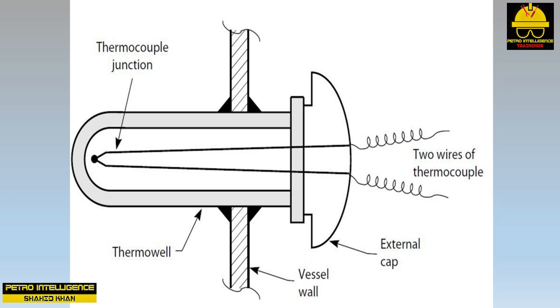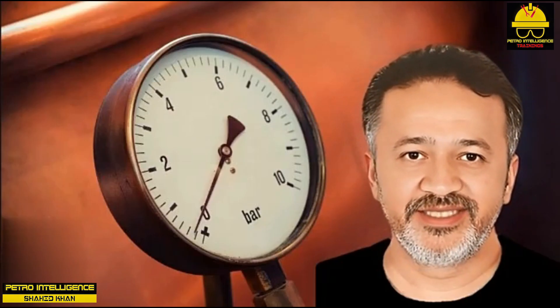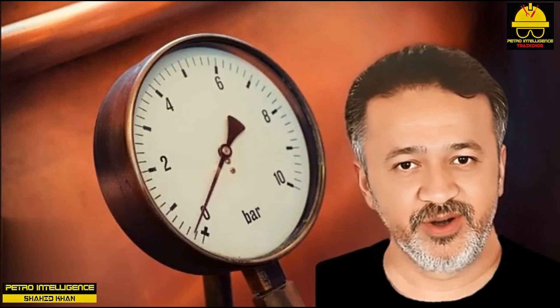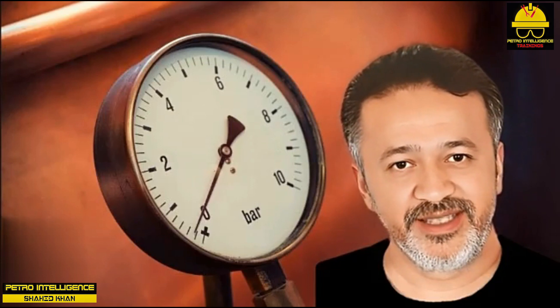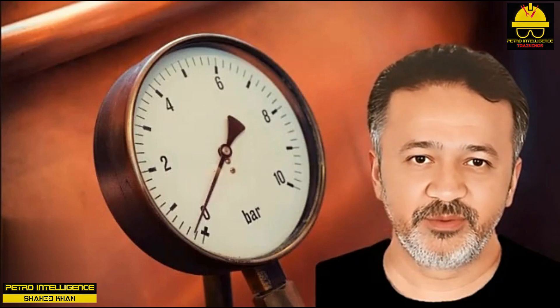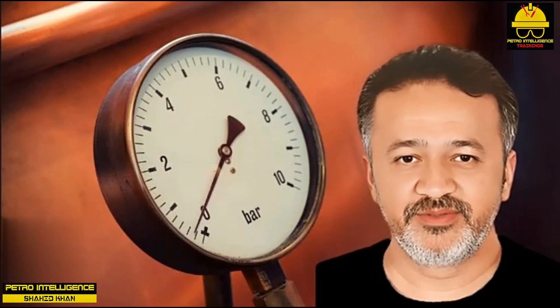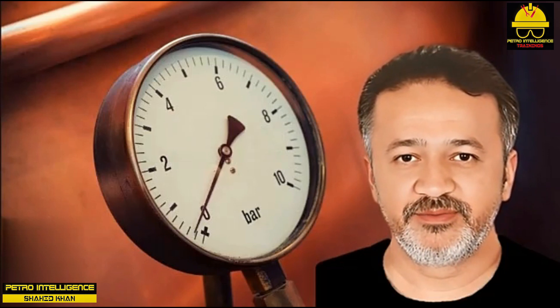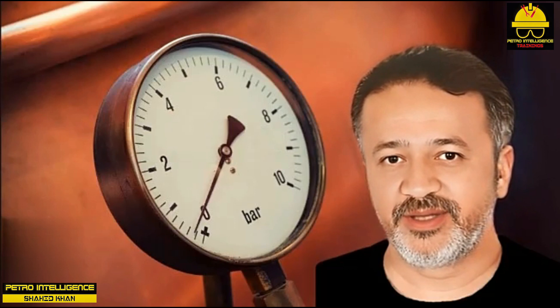The problem is that the external cap of the thermowell assembly radiates a small amount of heat to the atmosphere — normally this has negligible effect on indicated temperature. However, when the process temperature is 600 to 800°F, the thermowell is in a vapor phase and becomes coated with coke. The indicated temperature can drop by 40°F below its true value. To verify thermowell fouling, place a piece of loose insulation over the exterior thermowell assembly — if the indicated temperature rises by 5 to 10°F, fouling is confirmed.